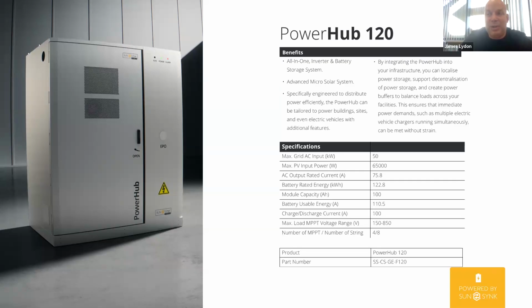So the 50 kilowatt, you can have up to eight strings in it. So if you want to put your PV into this, you can do. But yeah, the power hubs have been really popular, especially with companies where, as I mentioned earlier, they want to AC couple an existing system. So if you've got a building that's got 800 kilowatt of PV on the roof, but they've looked at the export data and some afternoons or weekends, they're exporting all this power. Instead of doing that and not getting paid anything or very little for it, that can then be diverted into this.